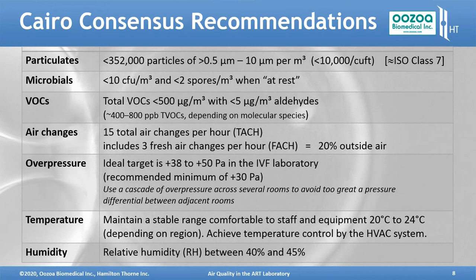This makes it cheaper to run in terms of not having to keep purifying and conditioning, in terms of temperature, all the fresh air. In terms of overpressure, which again is not basically the same as an ISO standard, the ideal target is between 38 and 50 pascals positive pressure in the IVF lab. The minimum should be plus 30 pascals for a modern facility. And to achieve this, you use a cascade of overpressure across several rooms. So you aren't trying to go from ambient to plus 50 pascals. It makes the doors quite hard to open.